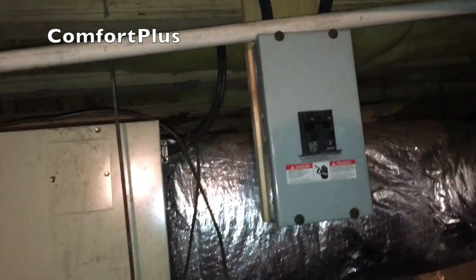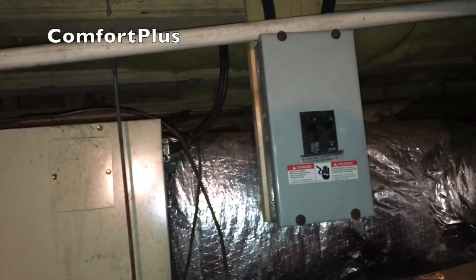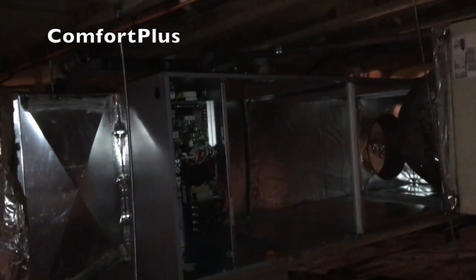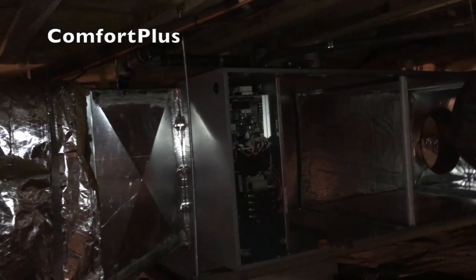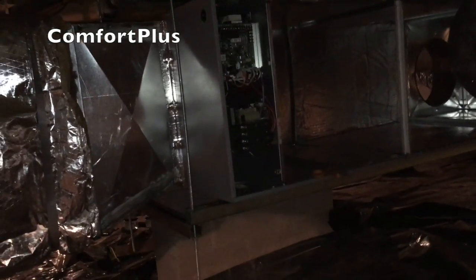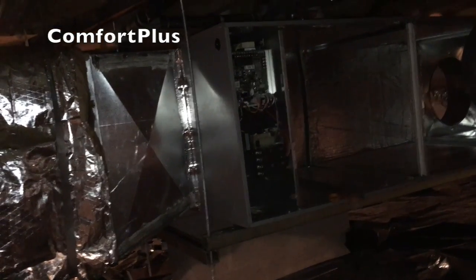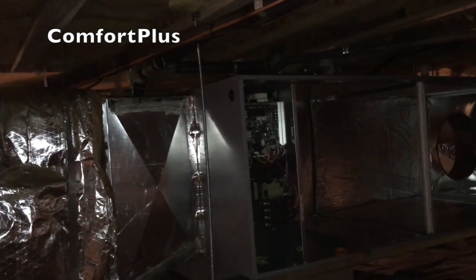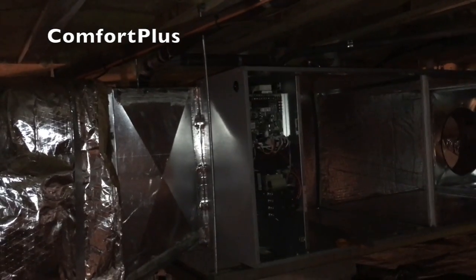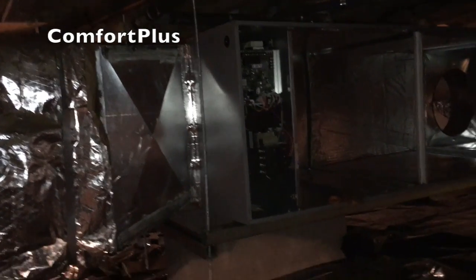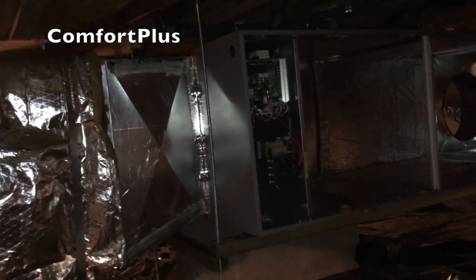That's a 60 amp circuit. I'll take it out and pull it over to the boxes down that way, so I'll pull it over to this air handler. I also need a 30. I got 15 kW in this one, so I'll have to run a new number 10 back to the panel for the extra auxiliary heat.